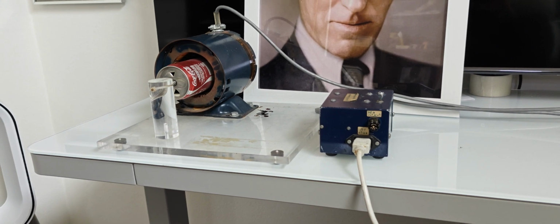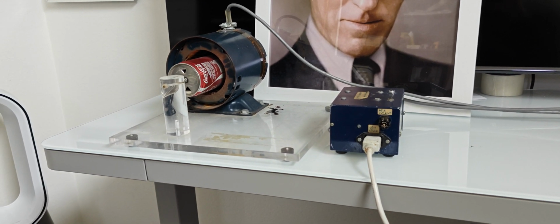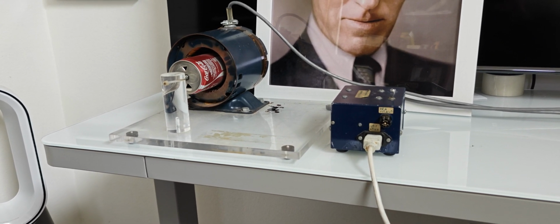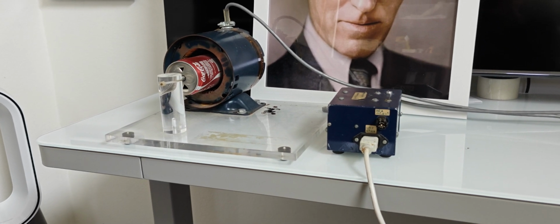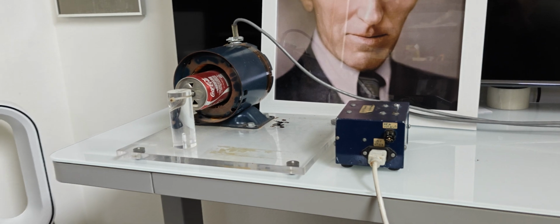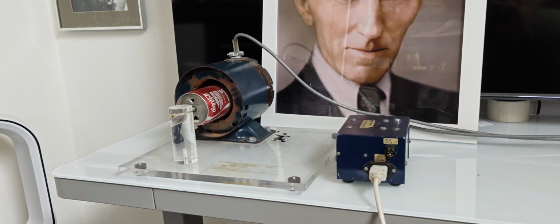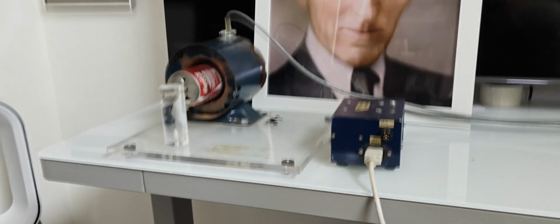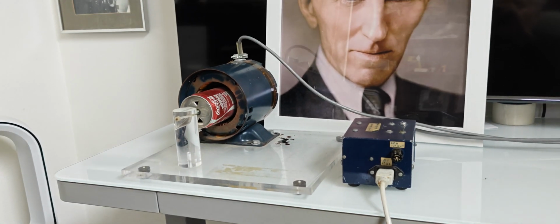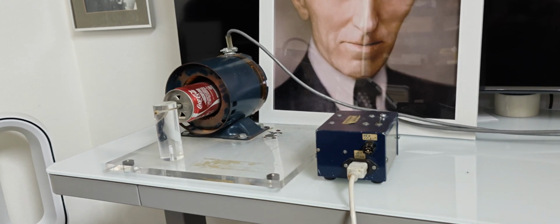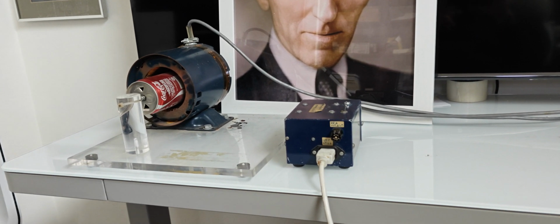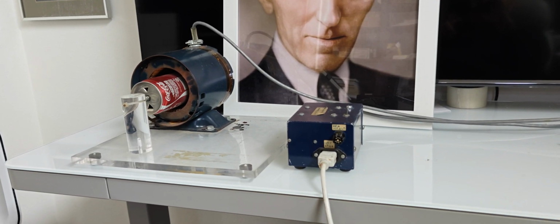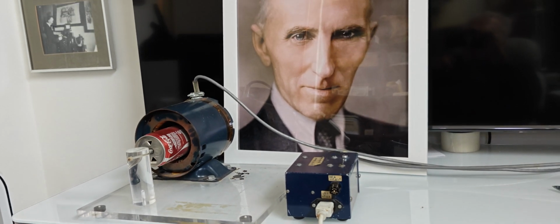Here, what I demonstrate, you cannot really operate this induction motor with a Coke can inside, because once you take the rotor out, you make a very low inductance, and there will be a huge current which will burn the stator winding. So what we had is in a box on the right.